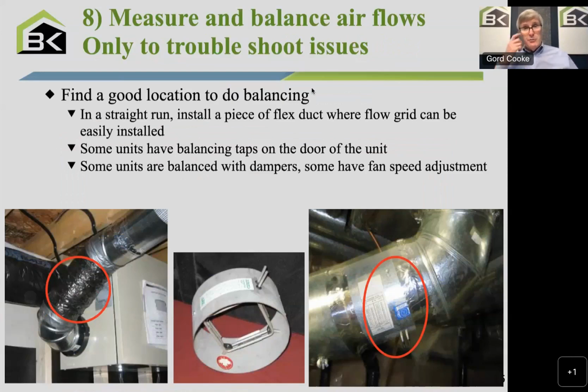The historic way of measuring that was with what are called balancing kits, and maybe many communities already have these. It's a simple little kit. It has a gauge in it. It has a couple of these. You're seeing in the middle what's called a flow grid, and they can be inserted into the line. So that 6-inch round flow grid over on the left, you just pull off that flex, insert that grid, and use a pressure gauge to take a measurement. It comes as a kit, and the kits are in the order of a couple hundred dollars, maybe $300.